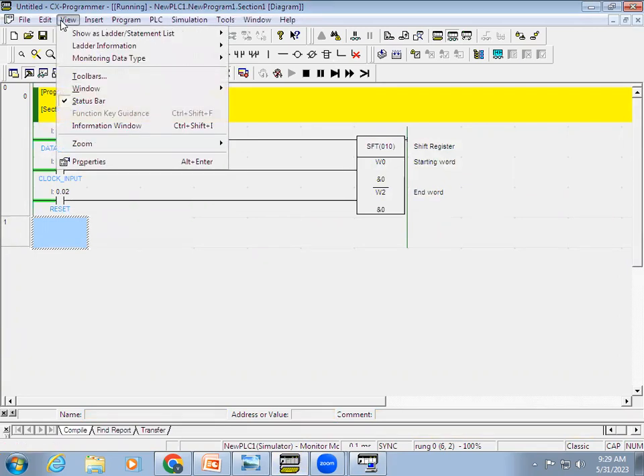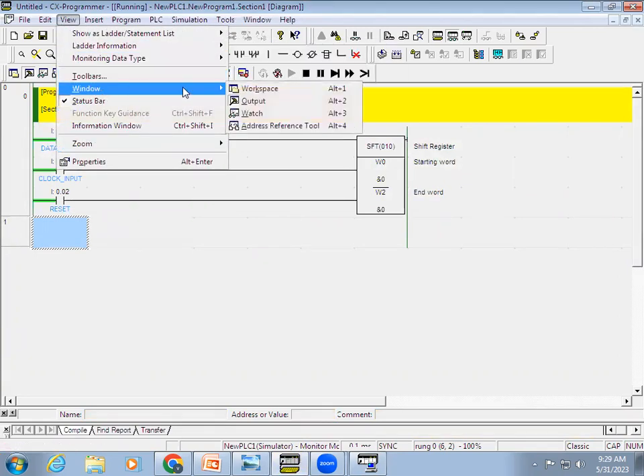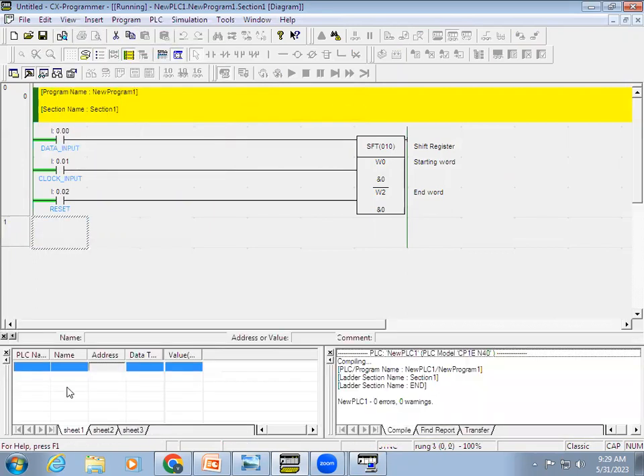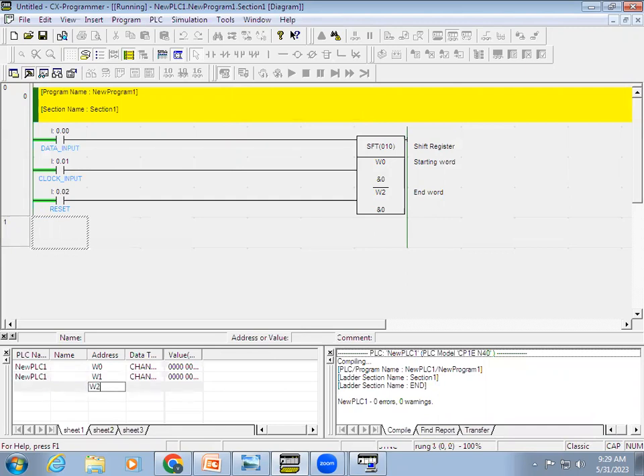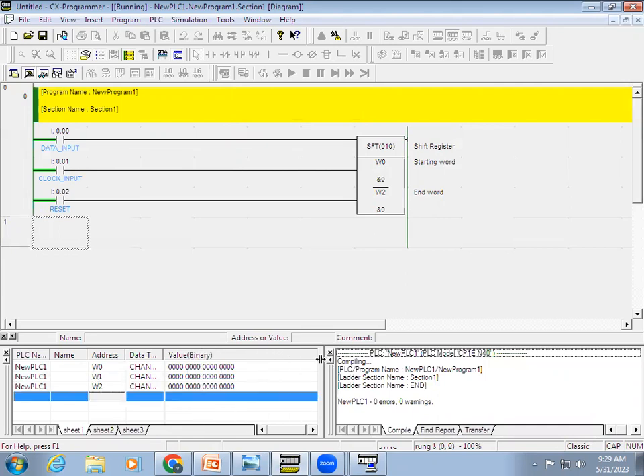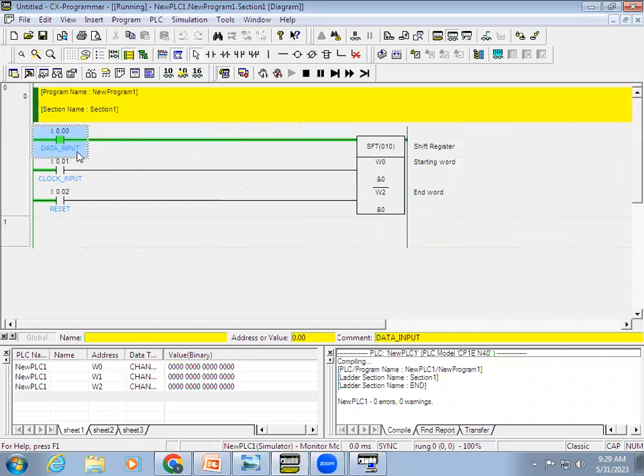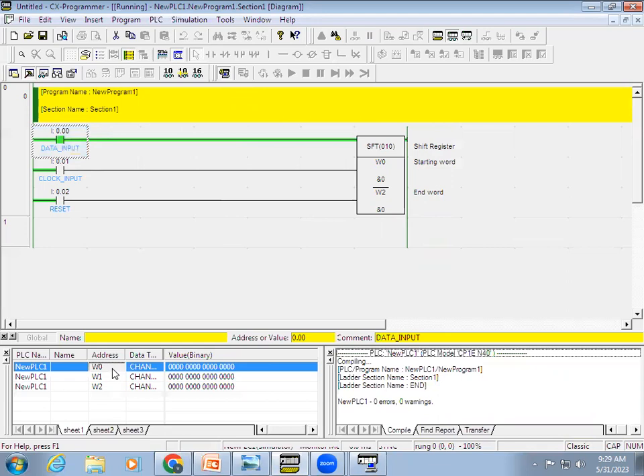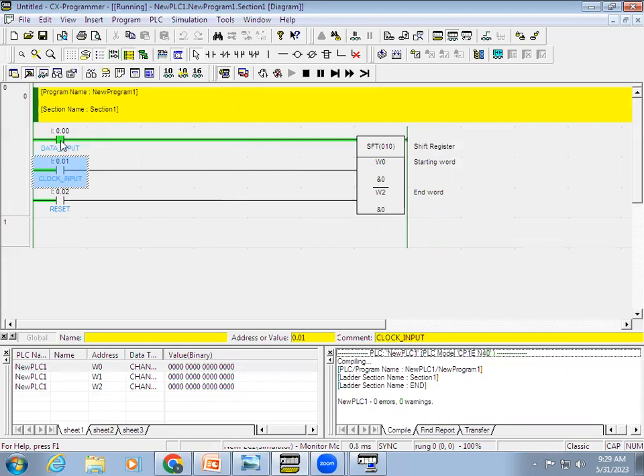To observe this we need the watch table, so I'll go to View > Windows > Watch and open the table. I'll add the three 16-bit addresses: W0, W1, and W2. You can see each address has 16 bits. Now if the data input is given as one, you can see that the true status is not yet accepted in the shift register — in W0 bit 0, the value has not been accepted. It will only accept when the clock input is triggered.